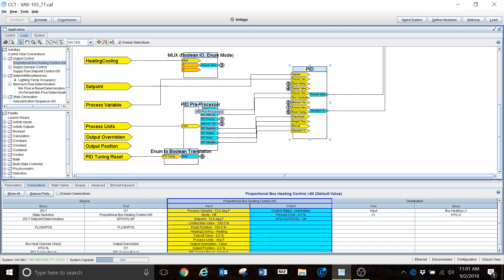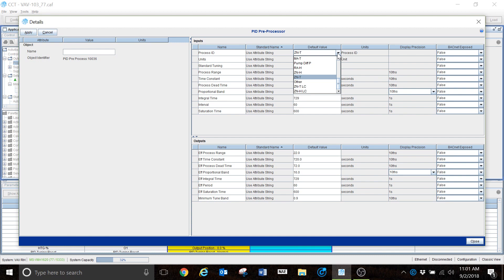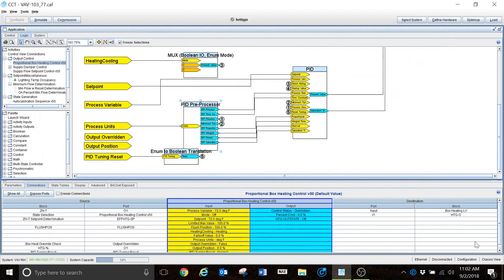This is a PID preprocessor. What this is going to do is basically tell the PID loop what it's going to be doing. If I double-click into it, you can see some of the same kind of information — process ID, zone temp control, that sort of thing. If I drop this down, I have to hit the Edit button before it will let me do that. This right here is all the different types of information that the PID loop can control — if you're going to be controlling zone temp, discharge air temp, all that sort of thing, this PID preprocessor is what tells the PID loop exactly what it's going to be doing.